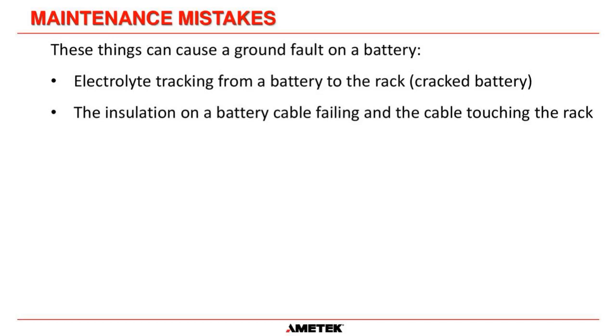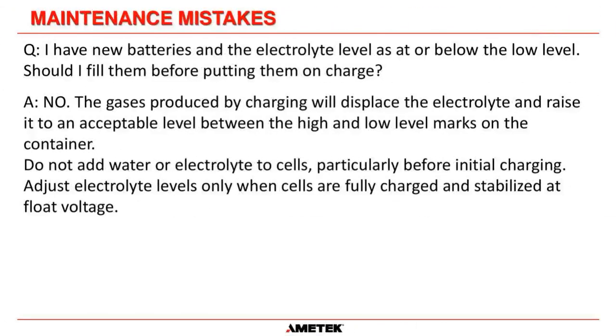And the other thing that can cause a ground fault is if the insulation on one of the battery cables has failed or is failing, and that cable is touching the rack, because the rack should be grounded. Okay, so that's really the only 2 things that can cause a battery ground. So it's very rare that either of those things are going to happen. So it's usually always your load circuits that cause ground faults.